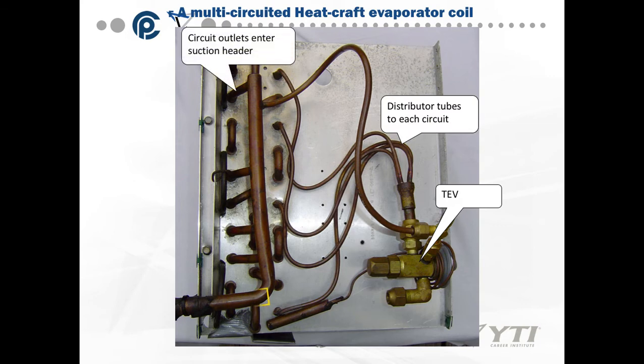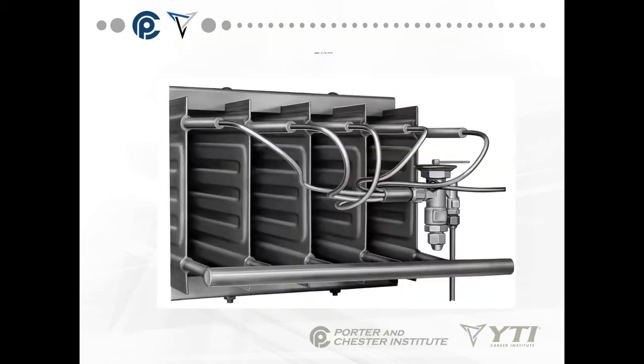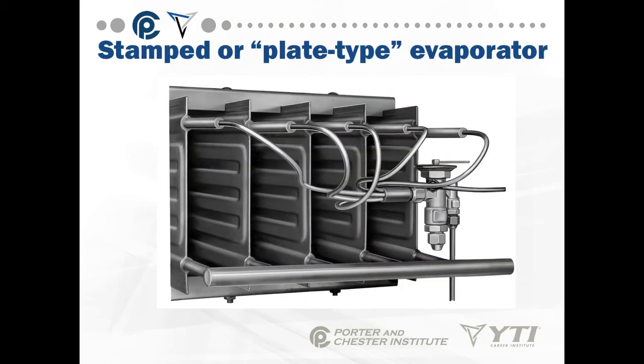The distributor sends refrigerant through a tube to each circuit, and the circuit outlets enter a suction header that returns to the suction line. A stamped or plate-type evaporator also uses a distributor, but instead of fins and tubes, it uses stamped plates where two sections are put together. These are used in ice machines and to cool liquids.